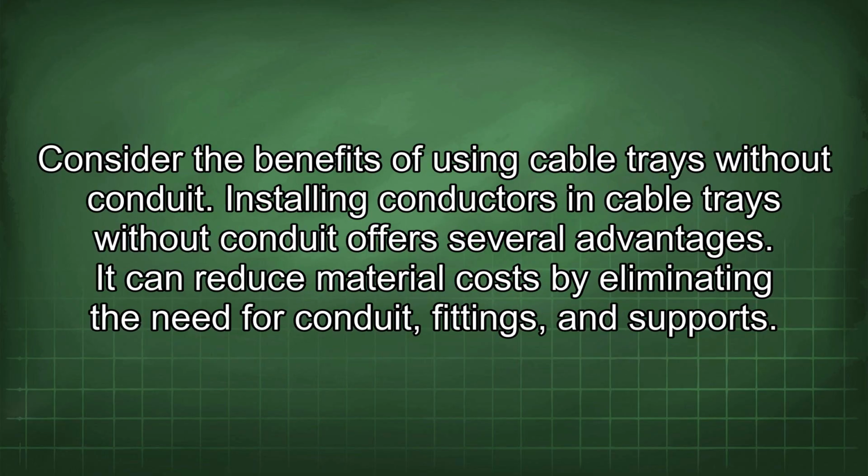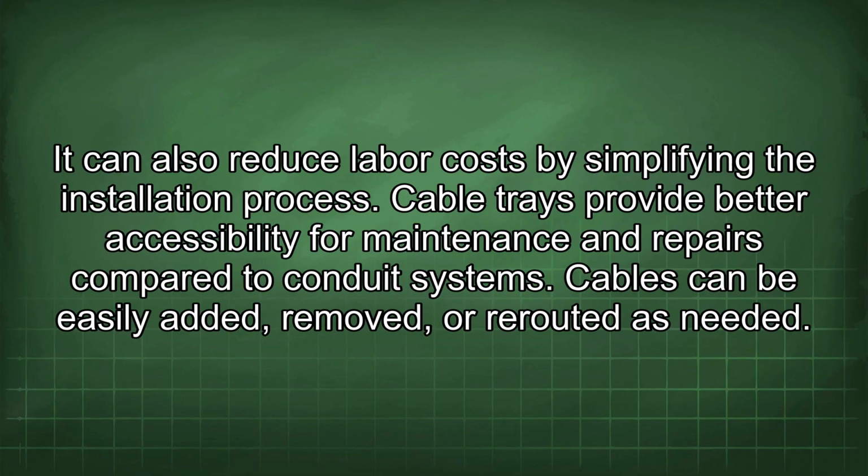Consider the benefits of using cable trays without conduit. Installing conductors in cable trays without conduit offers several advantages. It can reduce material costs by eliminating the need for conduit, fittings, and supports. It can also reduce labor costs by simplifying the installation process. Cable trays provide better accessibility for maintenance and repairs compared to conduit systems. Cables can be easily added, removed, or rerouted as needed.